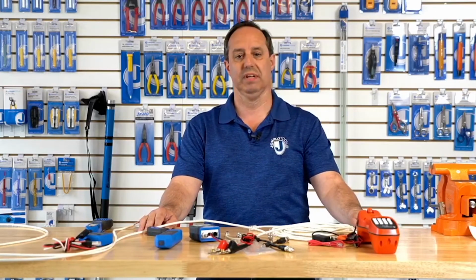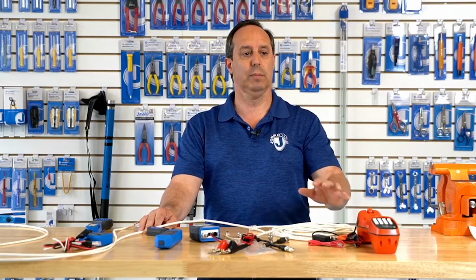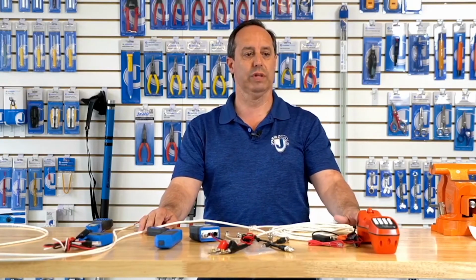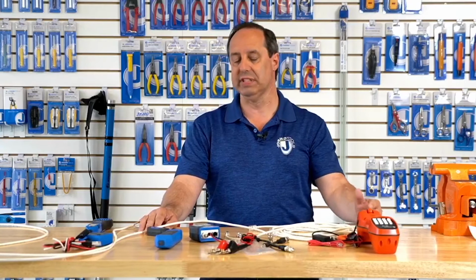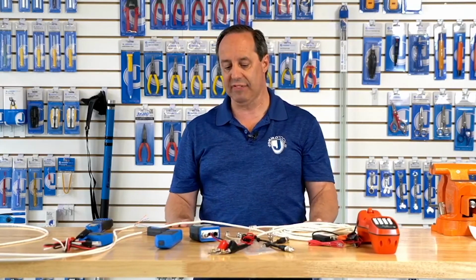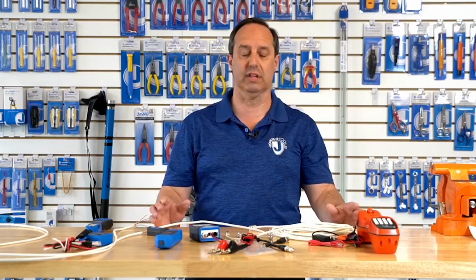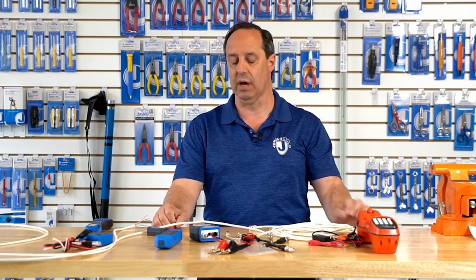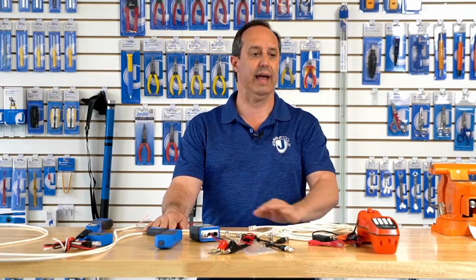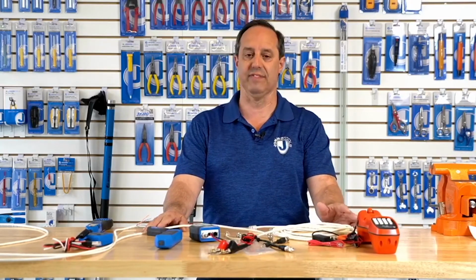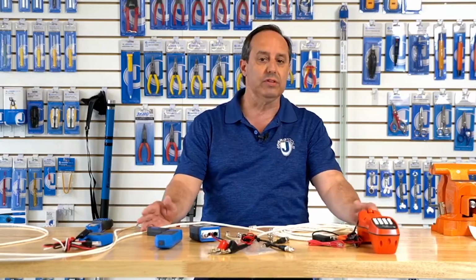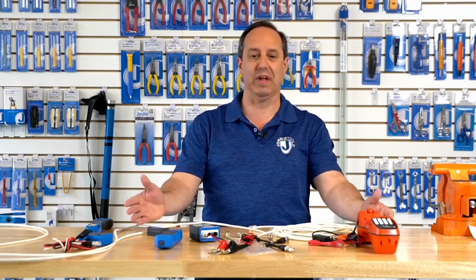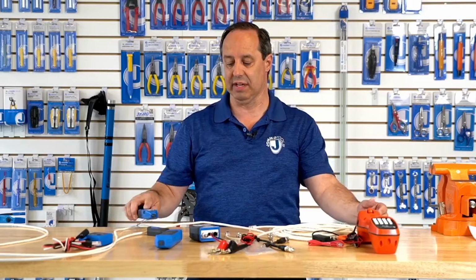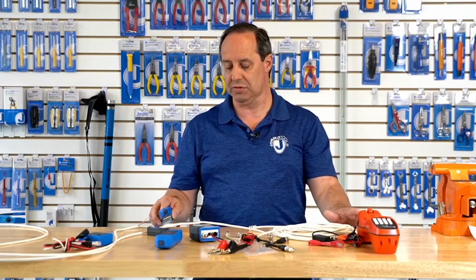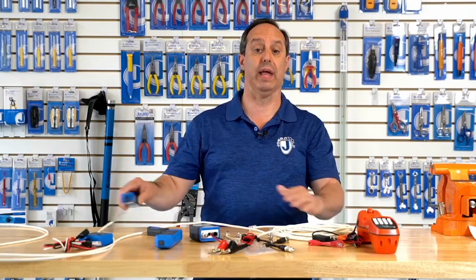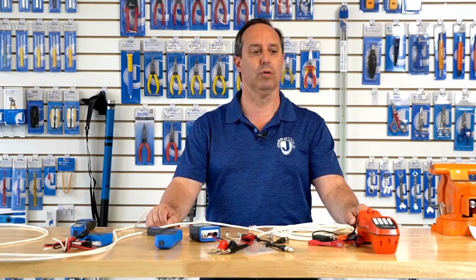Great question, and a very common one: does the probe have to make contact with the wire for it to work? The answer is no, it does not have to make physical contact with the wire carrying the tone. It just has to be very close, anywhere from a quarter inch, an eighth of an inch, to three-eighths of an inch, something in that range. If you're close to the source, it can even be a couple inches away and you'll still pick up the tone.